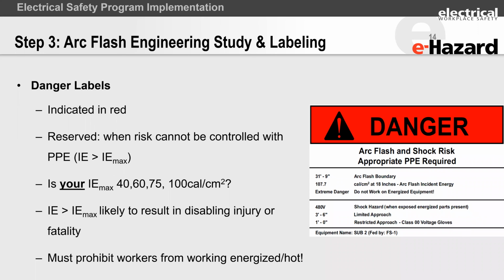So it has been observed in industry, because folks think, hey, arc flash is so dangerous that it's going to kill everybody, folks have gone out and stuck danger labels on every piece of equipment. They've even put out danger labels stating that the energy is less than 1.2 calories per square centimeter. And when you ask them, hey, folks, why did you do that? They say, oh, because of the shock hazard. Well, if you can protect against the shock hazard, and there has been training, there is a safety management system in place, there is adequate PPE, then folks, that is a hazard that can be protected against, which means it's a warning label, not a danger label. So please go back and have a look at the systems, because some of these may predate your arrival onto site. And I just want you to be aware of, use the right form of communication with your labels as well.